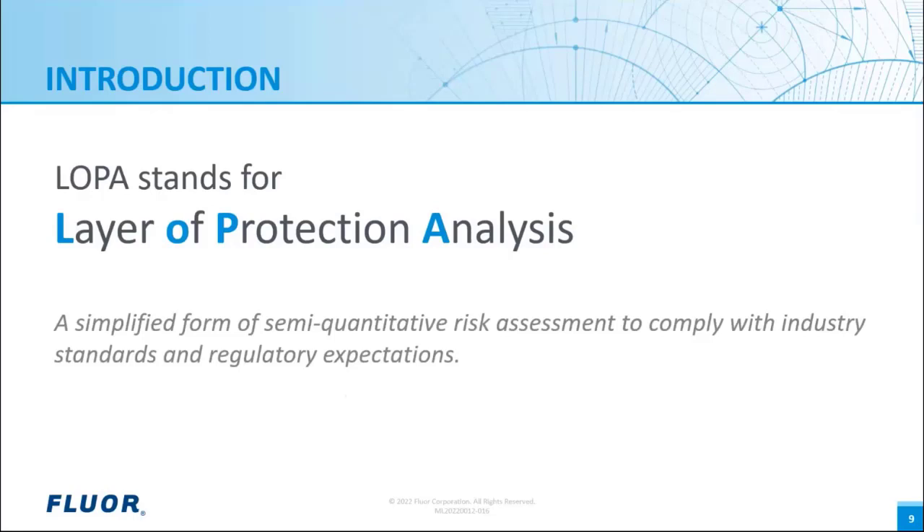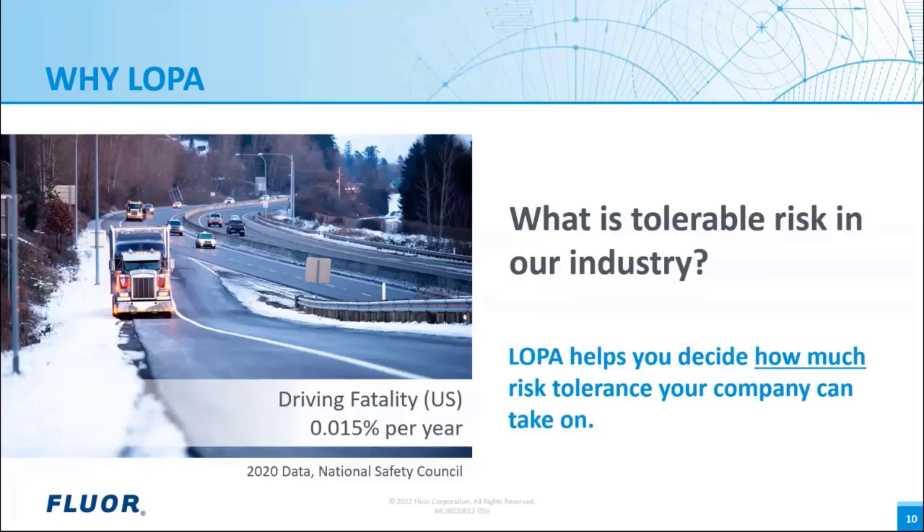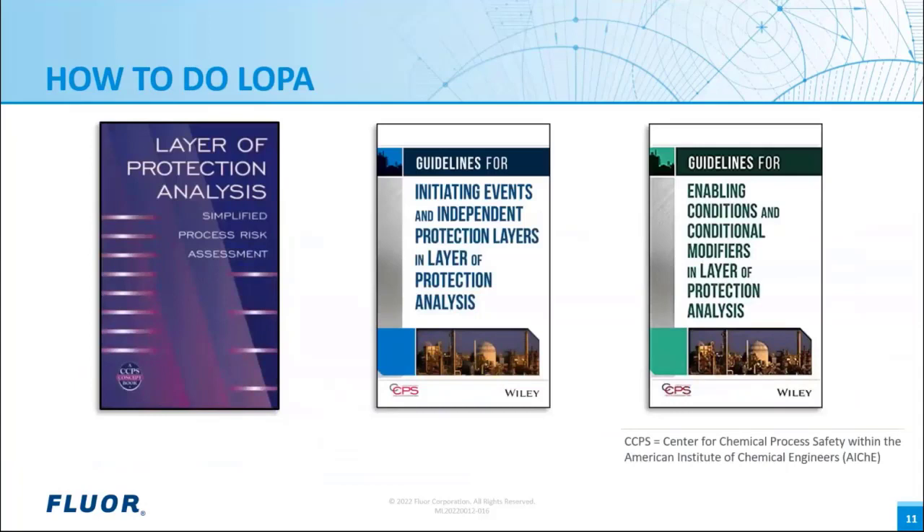LOPA is a simplified form of a semi-quantitative risk assessment to comply with industry standards and regulatory expectations on functional safety, as documented in IEC 61508 or 61511. Why should we apply this? Why should any industrial facility tolerate a risk factor higher than associated with driving a car? Acceptable might be the risk when driving a car, which is 0.015% per year for fatality in the United States. Tolerable might be a higher risk — for workers, between 0.15% and 1.5% per year. There is no life without risk, but you must investigate and document the risks to know and decide if they are acceptable or at least tolerable. That is why LOPA can help you document this clearly and show if further protection is required or not.